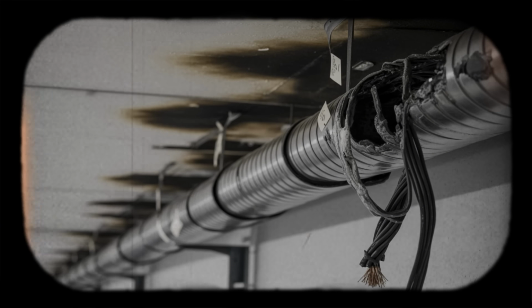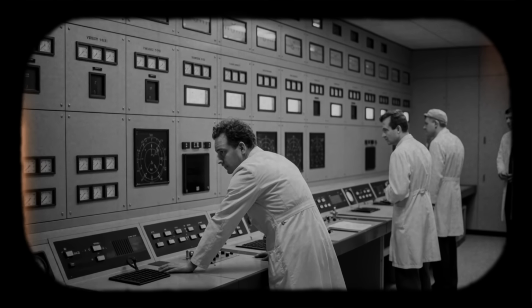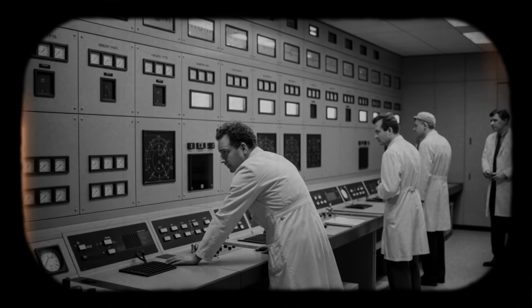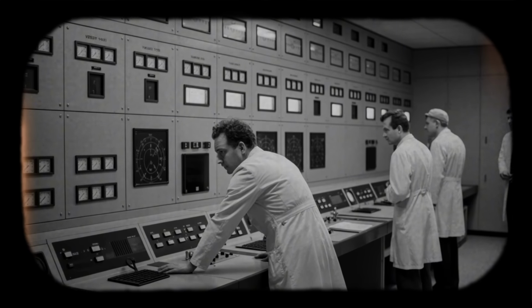Expected response: even after a reactor scram, main or emergency feedwater should remain available from multiple trains, backed by separate 6 kV buses and emergency diesel generators. Actual situation: destroyed cables meant all main and emergency feedwater pumps were unavailable. The plant was approaching a station blackout, loss of off-site power combined with loss of on-site emergency power, and simultaneously a loss of heat sink scenario.